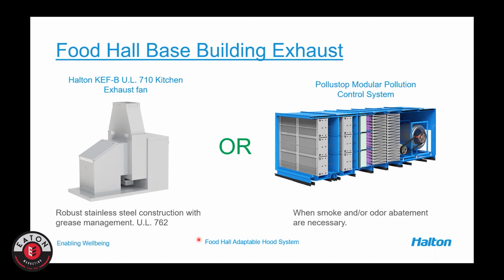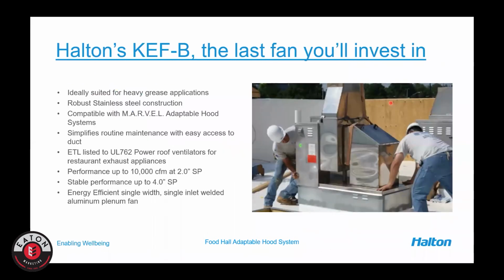This particular fan is a fan we use for a lot of different applications, but it's a stainless steel utility blower with a grease containment system that can either be collected in the base of the fan, or we can actually pipe it back down to the hood itself. This particular fan, we have the ability to design up to about 10,000 CFM, and we'll get very stable performance with this fan up to about 4 inches of static pressure.